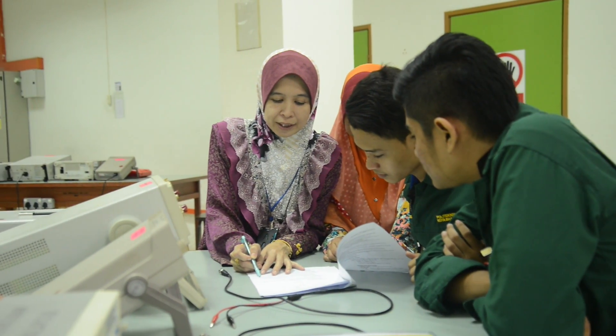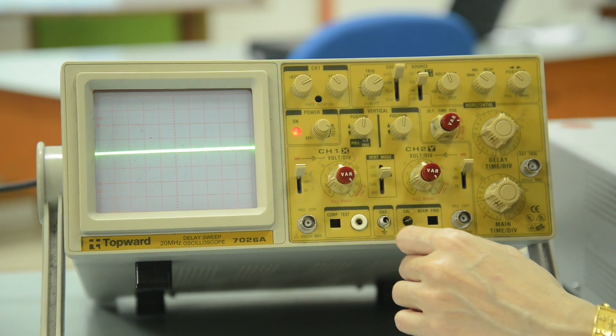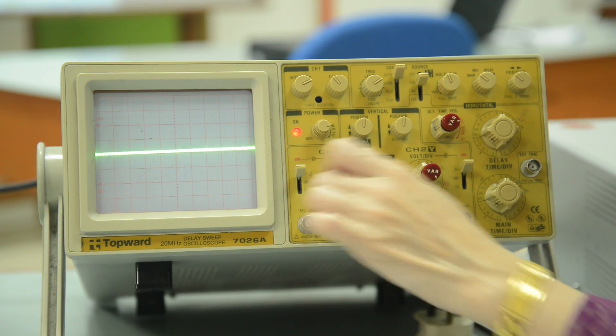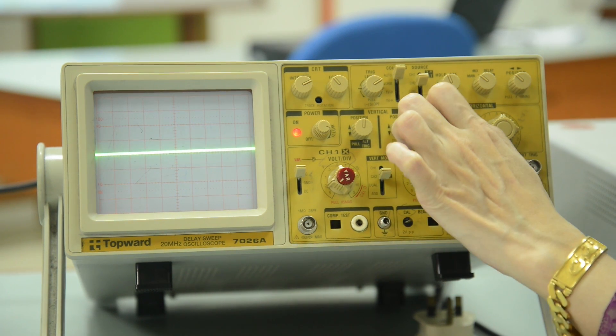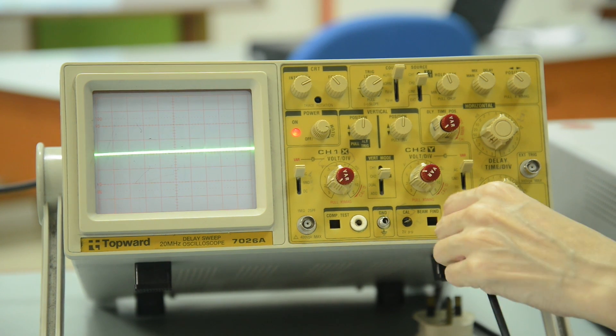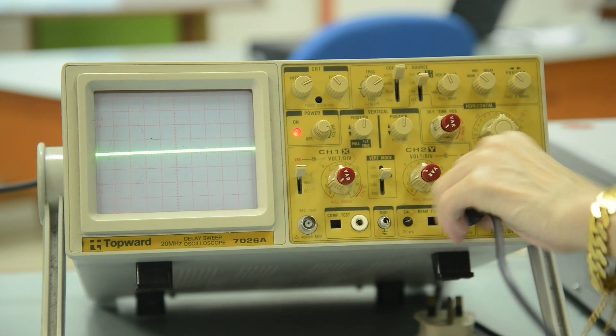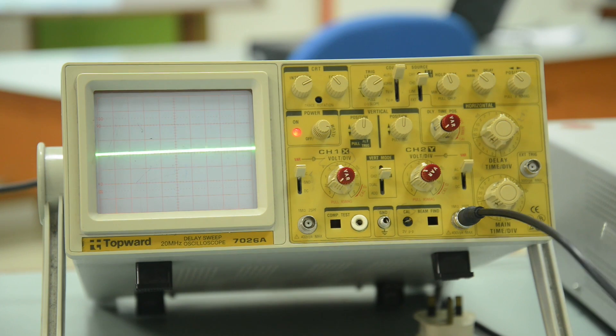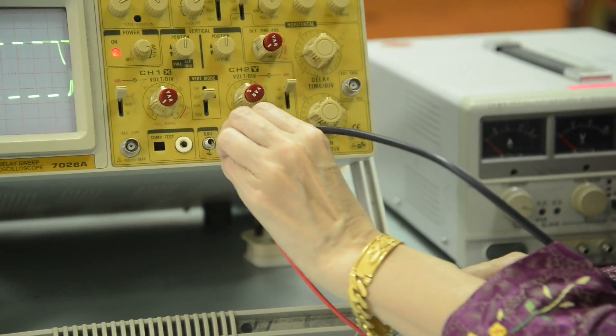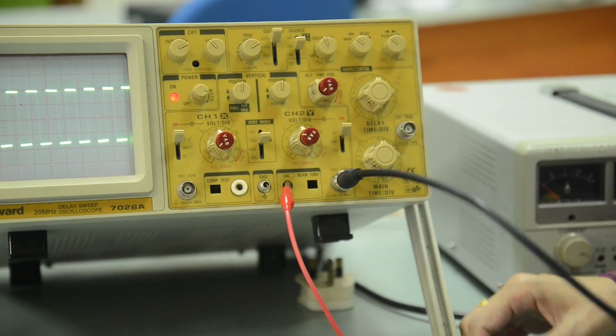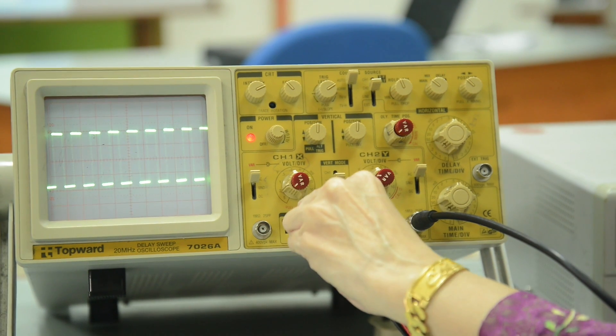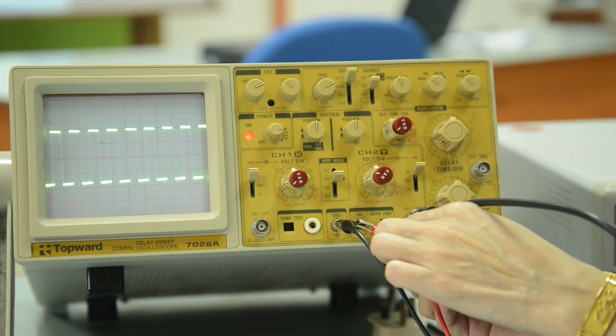We use 2 millivolts per division. Then we connect the probe to channel two, CAL, and ground. After that, we will get the waveform with the peak-to-peak value.